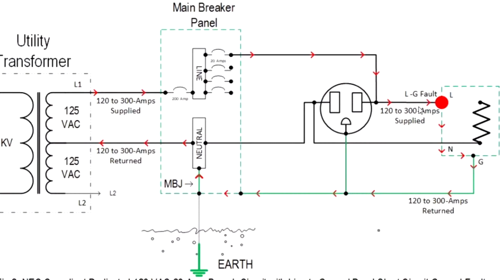And it could be as high as 300 amps if this 14 gauge, 12 gauge, if you're going by code, were a very short circuit, very close to the panel, versus, say, a long circuit out to the other end of the house, where you may only have 120 amps.